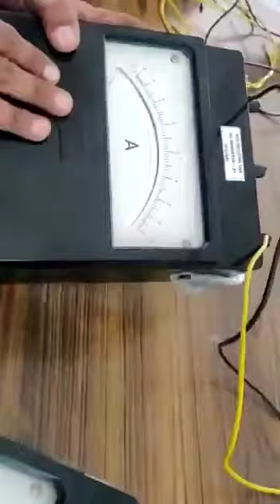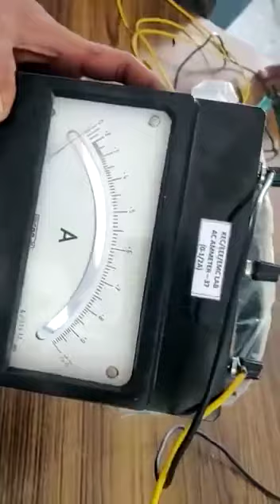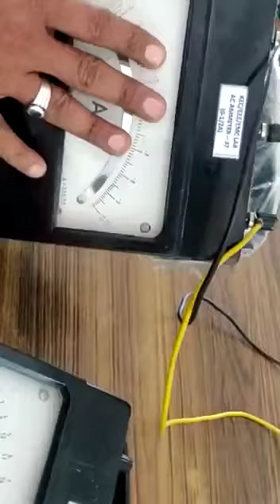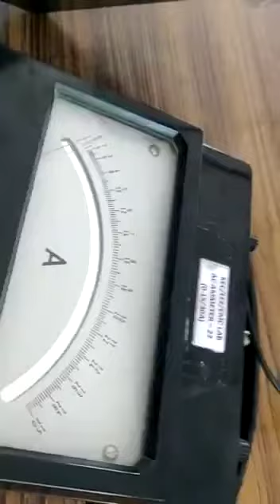So when this reading is multiplied with 10, 10 is nothing but ratio of CT, that is 50 by 5. You will get the actual current that is flowing in the load. This ammeter tells you whether the CT reads correctly or not. So primary current I1 is given by K into I2. First measure I2, multiply with K, that is your I1. That I1 is checked with this meter also. If error is present, you have to compute the error and calibrate the CT accordingly. That is the exercise.